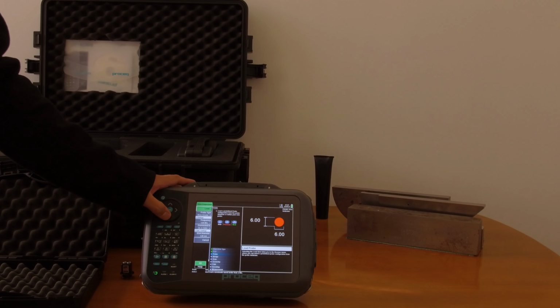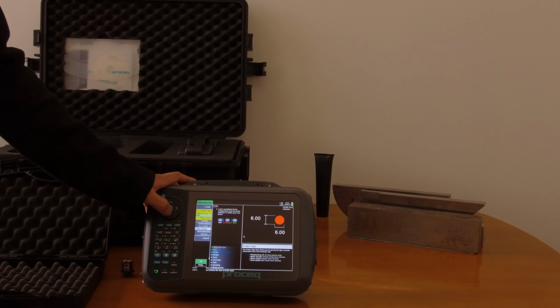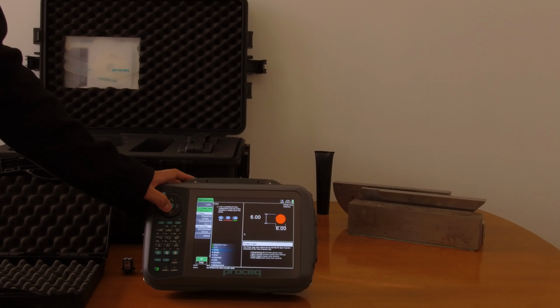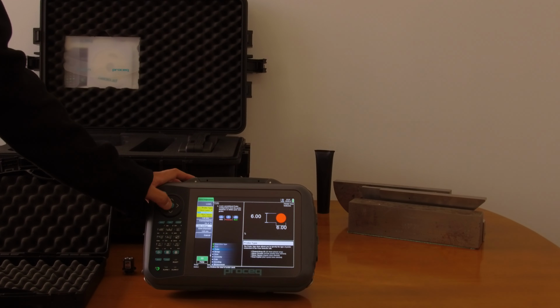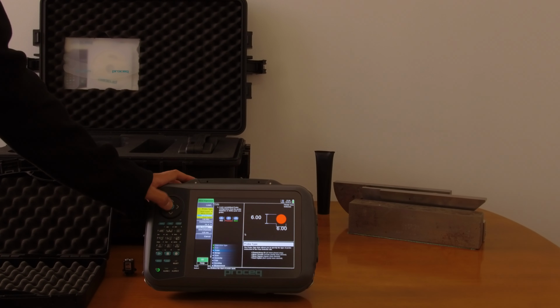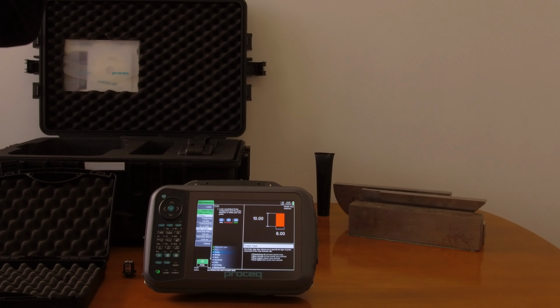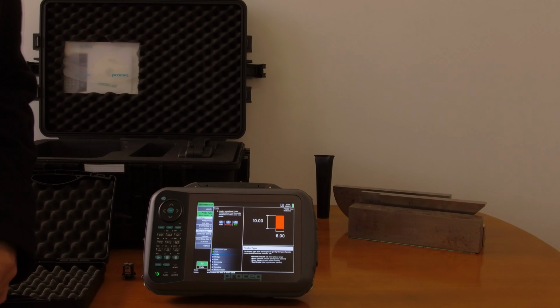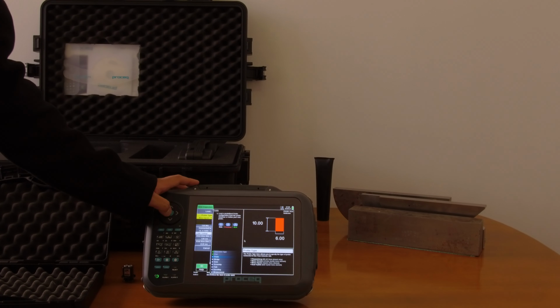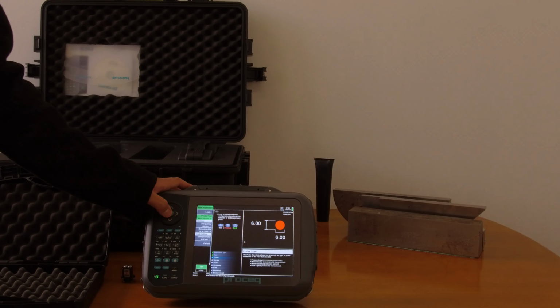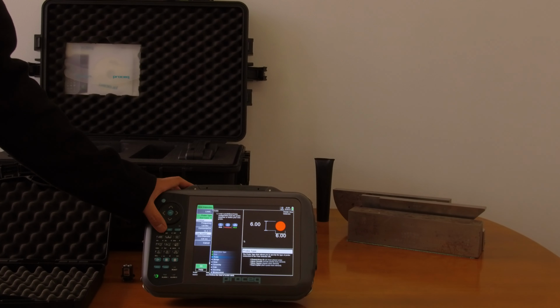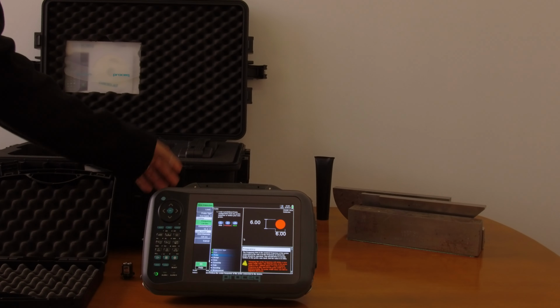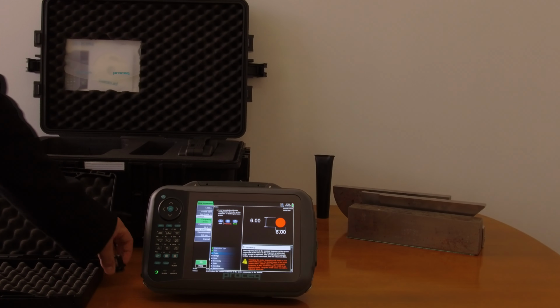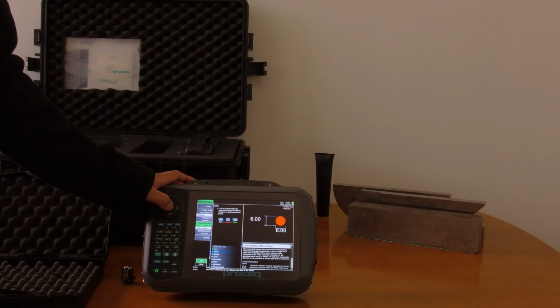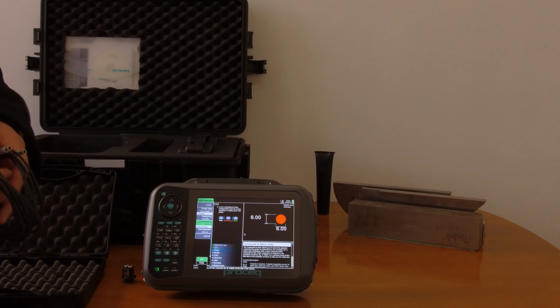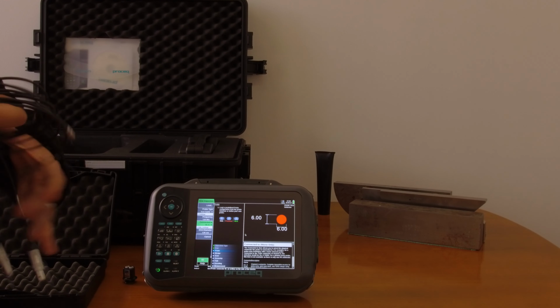Okay, so then we're going to nominate our probe type. I'm using a dual crystal, so I'm going to nominate dual crystal. You can also use a mono square and a mono circular, and questions will come up about that. For example, with the square, it'll come up with questions about the dimensions of the square. With the mono circular, it'll just be about the total diameter, and with the dual crystal, it's the same. So we're going to nominate a frequency. I've got a 5 megahertz probe here, so we're just going to put that there, and then we'll nominate the channel that we've connected that to. I'm going to opt for channel A.